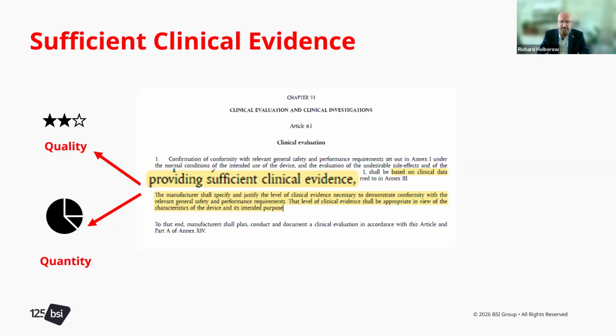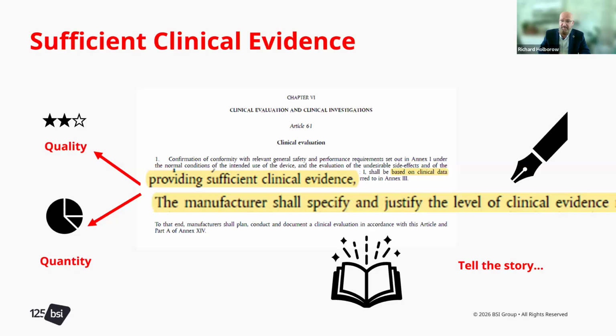And what the manufacturer is required to do is really to specify and justify that that clinical evidence is sufficient. It's not actually the notified body's role or responsibility to make the argument on behalf of the manufacturer. It's a notified body's role to validate or consider whether the manufacturer's justification is appropriate in the context of that device. And what is really helpful for manufacturers is when they tell us the story. So when we understand the background of the device as to why it's an orphan device, why it's used in pediatrics, for example, that really helps us to understand the technology, understand where its intended use is, and even what your expected sales volume might be, or the use of that device in the clinical setting. And again, the proportionality then allows us to apply the legal framework in a proportional and pragmatic way as well.